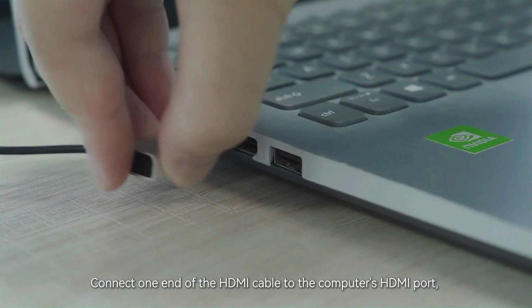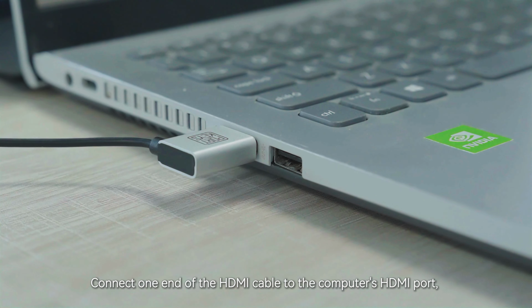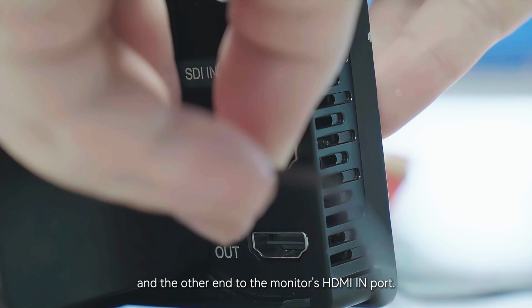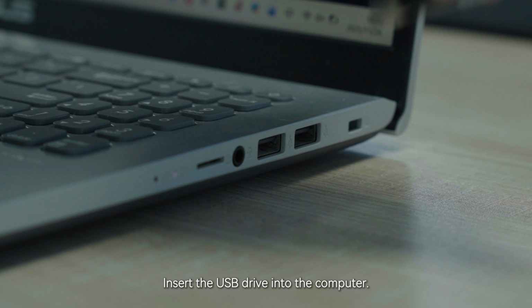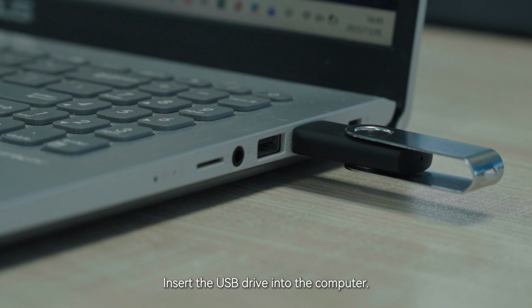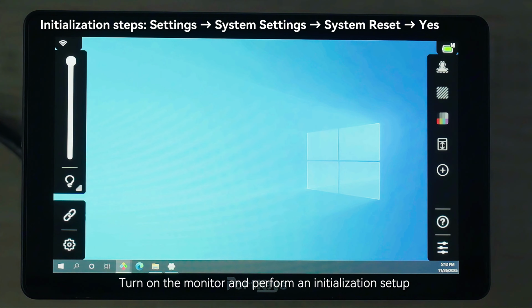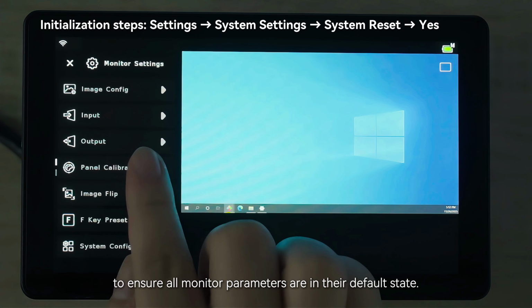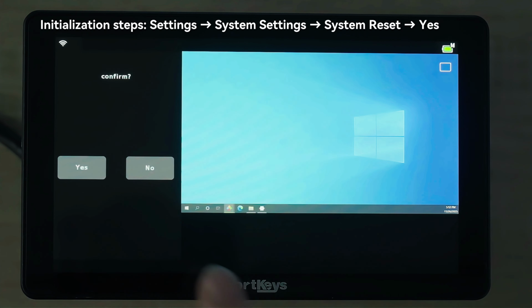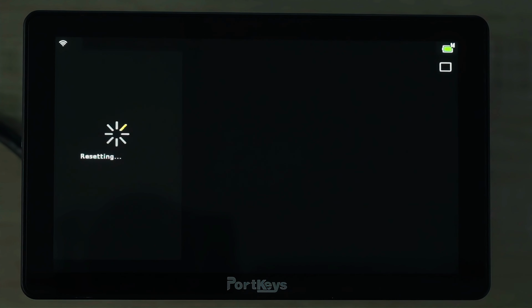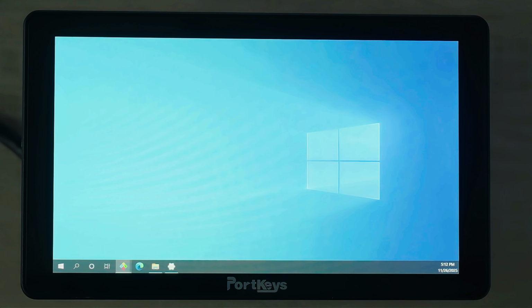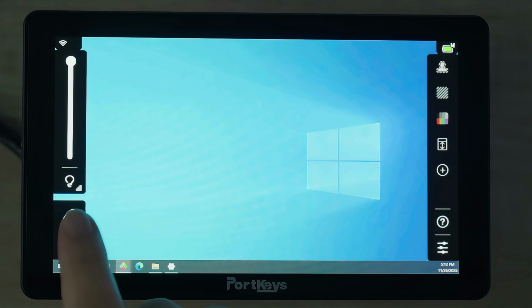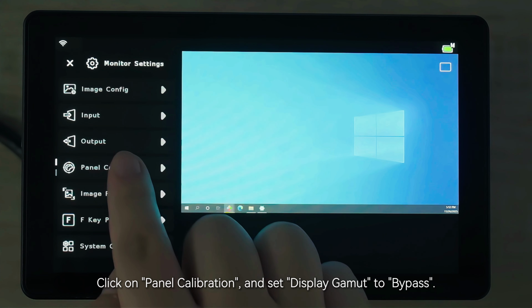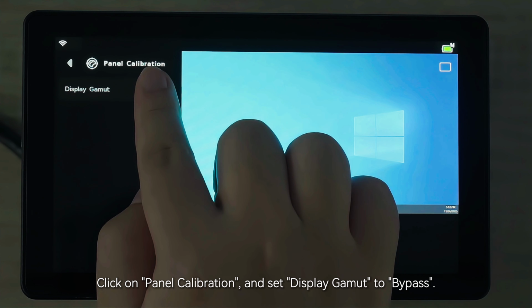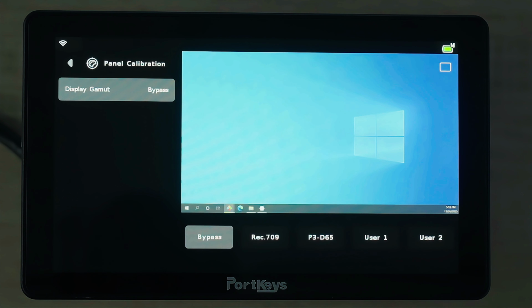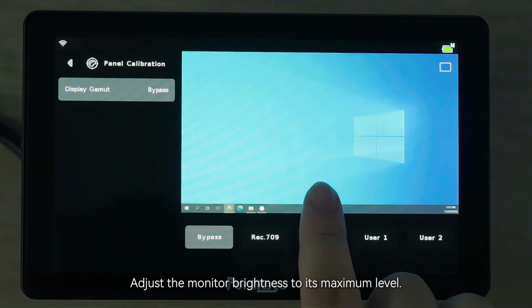Connect one end of the HDMI cable to the computer's HDMI port and the other end to the monitor's HDMI in port. Insert the USB drive into the computer. Turn on the monitor and perform an initialization setup to ensure all monitor parameters are in their default state. Click on Panel Calibration and set Display Gamut to Bypass. Adjust the monitor brightness to its maximum level.